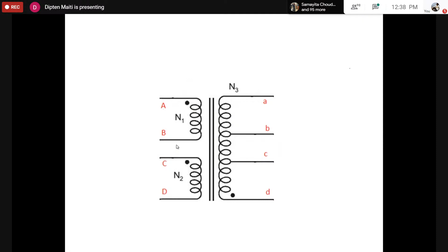We would make parallel connections for the coils to modify the transformer characteristics a bit. How do we modify? If we connect two terminals, let's say the voltage rating for this transformer is 110, and the voltage applied across A and B is 110, the voltage measured across C and D would also be 110. However, the voltage measured across small abcd would be around 220.